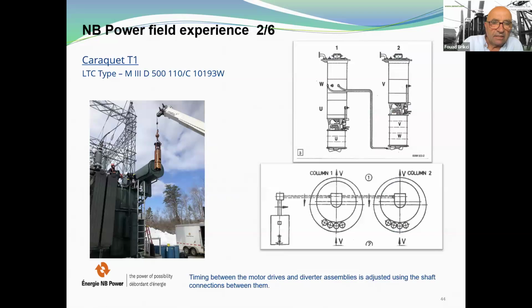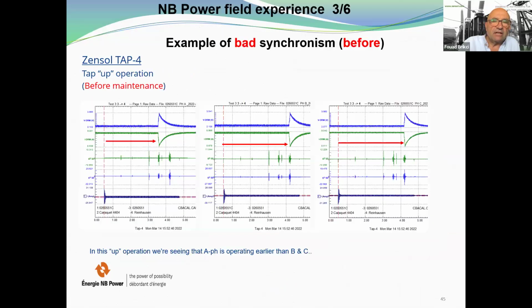Here it's to explain the timing. So you have a complex tap changer, because the timing between the motor drives and diverter assemblies is adjusted using the shaft connections between them. So the adjustment is not easy. Here I have used only the main results of this presentation.